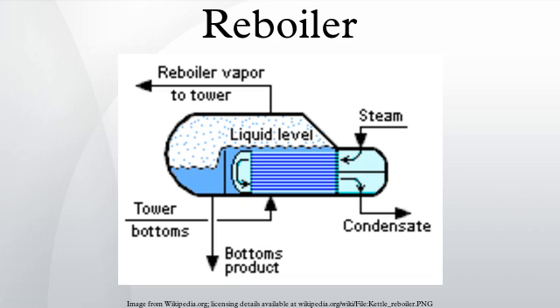Thermosyphon Reboilers: Thermosyphon reboilers do not require pumping of the column bottom's liquid into the reboiler. Natural circulation is obtained by using the density difference between the reboiler inlet column bottom's liquid and the reboiler outlet liquid-vapor mixture to provide sufficient liquid head to deliver the tower bottoms into the reboiler. Thermosyphon reboilers are more complex than kettle reboilers and require more attention from the plant operators. There are many types of thermosyphon reboilers including vertical, horizontal, once-through, or recirculating.